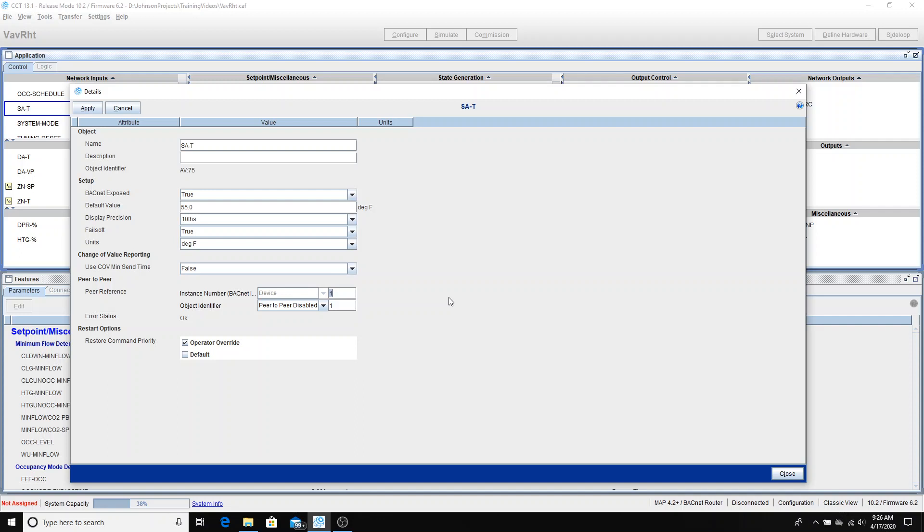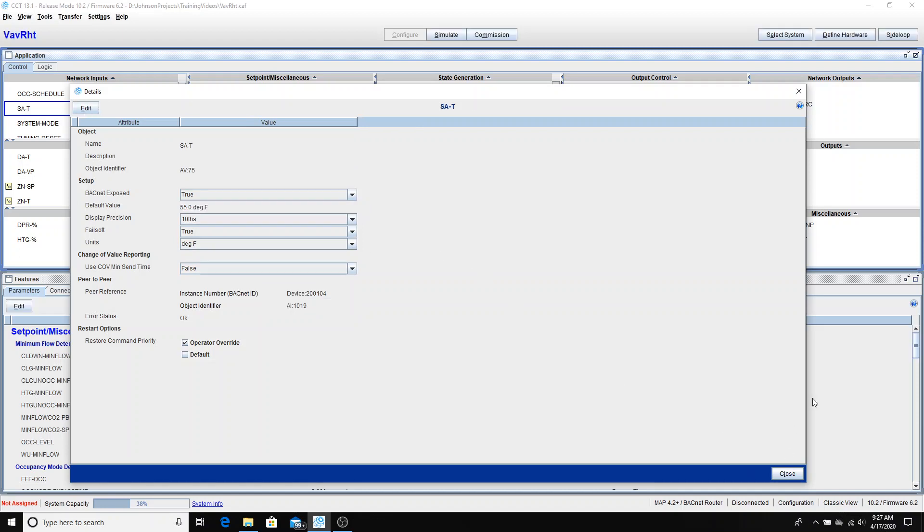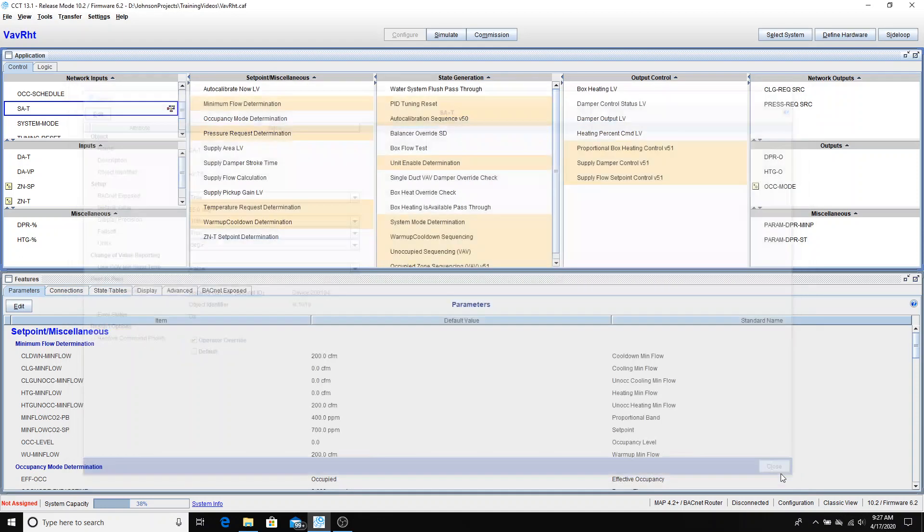I'm once again needing to put in the instance number from my air handling unit. So from the last video, we know that that was set to 2001-04. 2001 being the network number that I chose for that BACnet network, because that is the MAC address of the air handling unit. Now the object identifier that we just looked at, analog input 1019. I'm going to apply and close. Now you can see the little peer-to-peer icon exists here. It tells me that that's been configured.